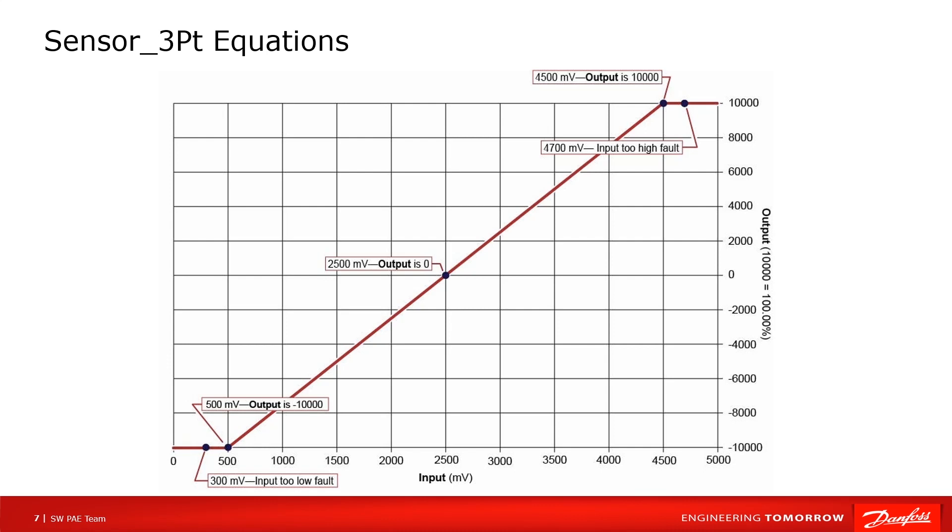We can find in the trace, when input is at 2500, the output is 0. When input is lower than 500, output remains at minus 10000. Fault points are 300 and 4700.